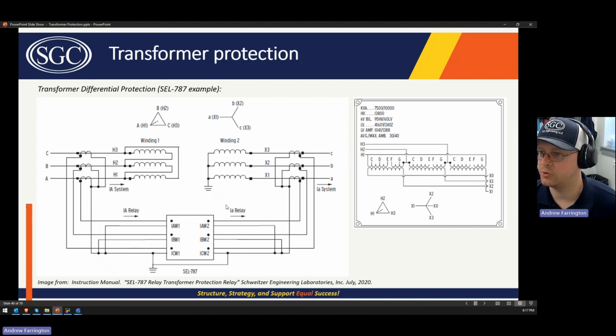Like I said, the transformer is a delta-Y transformer. Both of the CTs are wired in a Y configuration. Neither is wired in a delta. That'll be important for our settings in a moment, but you need to pay attention to that. And then, like I said, on the low side, we have the low side A current wired into the A current input, B to B, and C to C. And the polarity dots are all as you would expect. You guys have had the elementary diagram classes and relay one-line diagram classes, so you know that this is typical, but if that's not the way that your relay is wired, it's going to change these settings. So don't take it for granted that that's the way that your relay is wired.